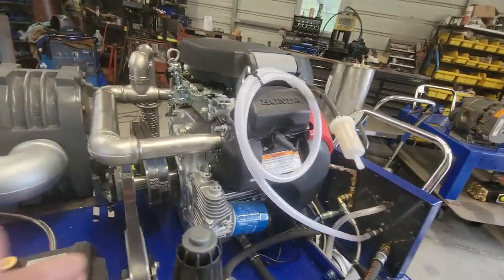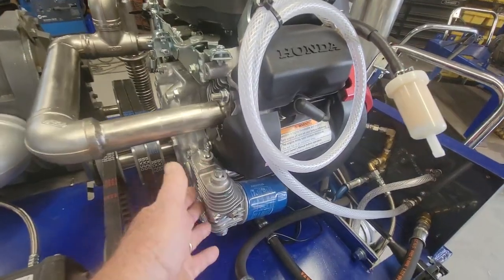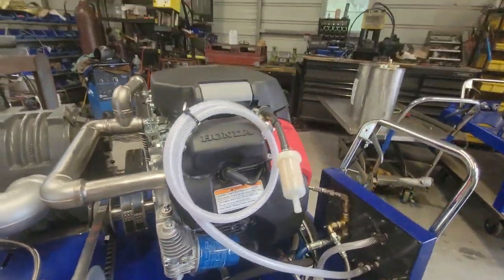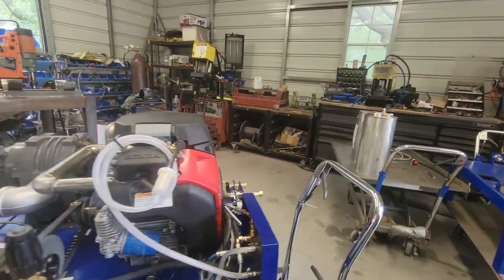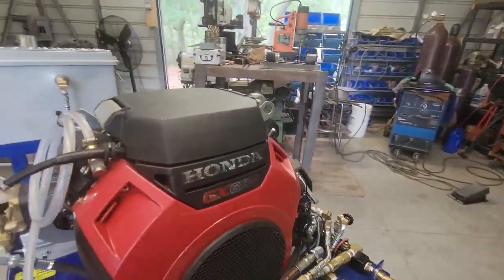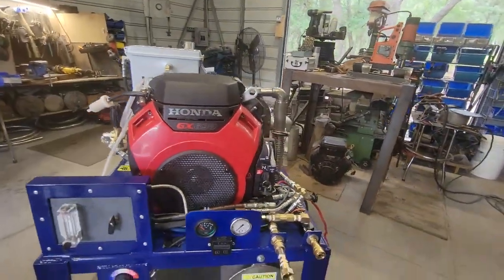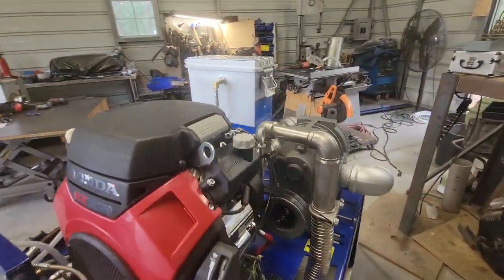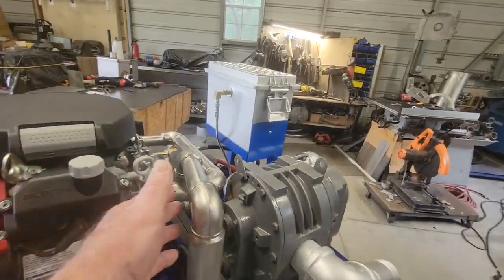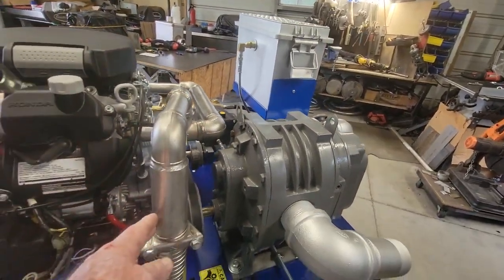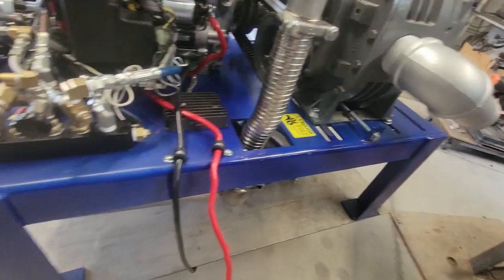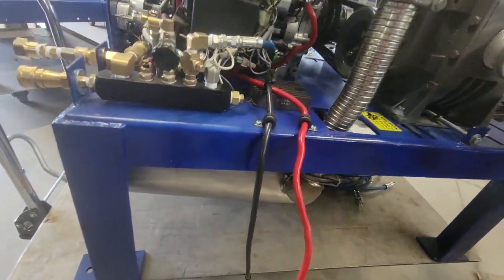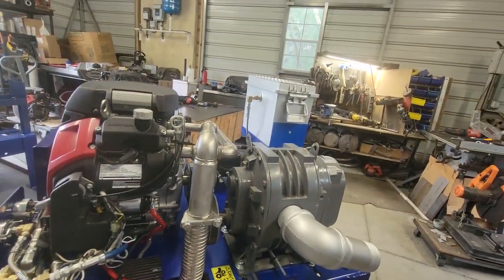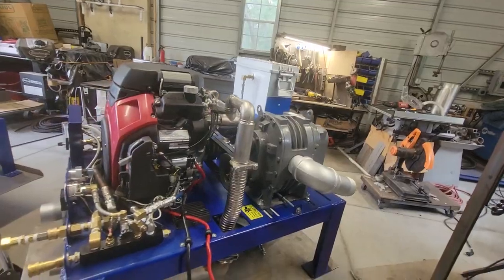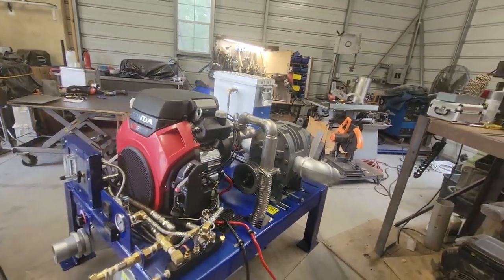And you can see our cooler for the oil—look at that cooler, that's beautiful. These Honda engines, the GX690, have been out for a number of years. Very dependable, a lot of torque, and they generate good heat transfer into the pipes. As the exhaust comes down through this stainless flex hose, it goes into our heat exchanger and produces beautiful commercial-rated heat.